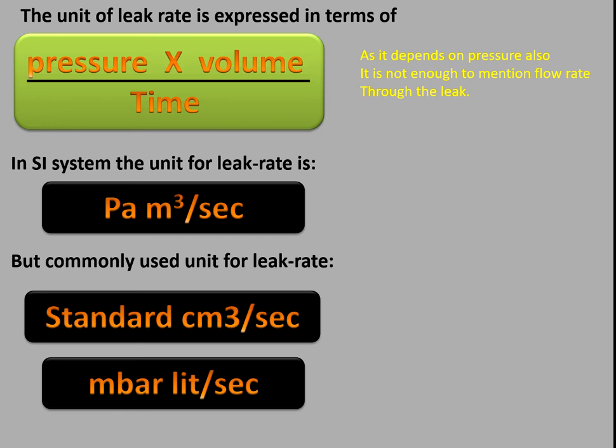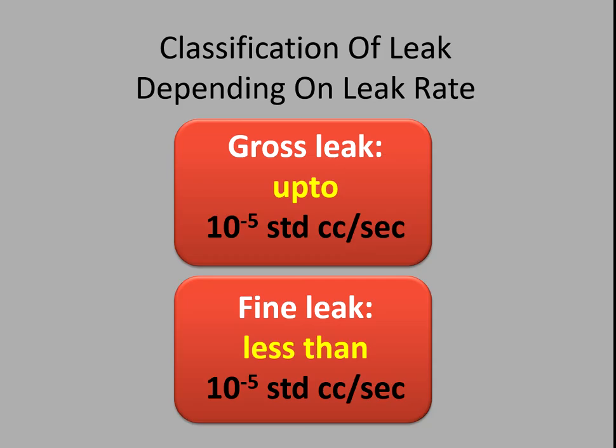The unit of leak rate is expressed in terms of pressure multiplied by volume divided by time. In the SI system, the unit of leak rate is Pascal meter cube per second. Commonly used units for leak rate are standard cubic centimeter per second and millibar liter per second.